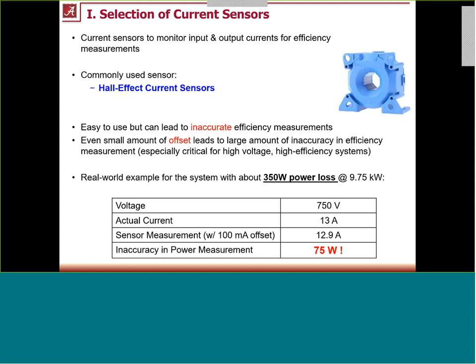What we found is that when trying to quantify the efficiency of this converter, these small offsets can lead to substantial error in our efficiency computation. For example, at 9.75 kilowatts, a measured loss of 350 watts, if the actual current is 13 amps but the sensor has a 100 milliamp offset, that gives an inaccuracy in the power measurement of about 75 watts. So we determined that the resolution and accuracy of these current sensors were insufficient for accurately quantifying the characteristics of this converter, so we ended up swapping to shunts.